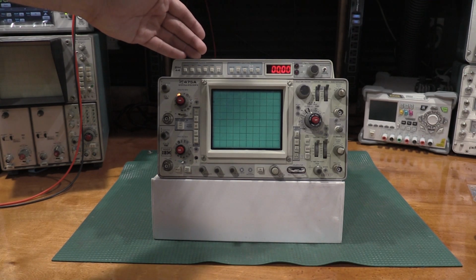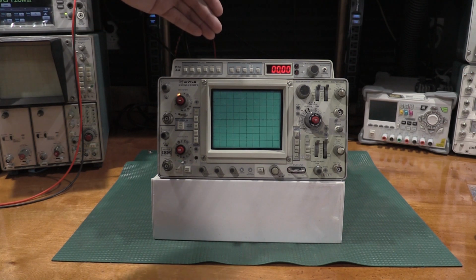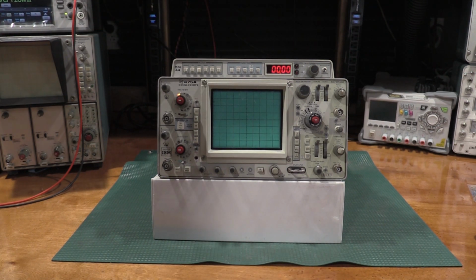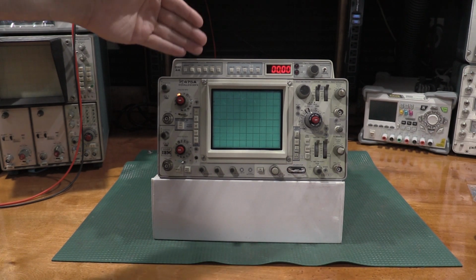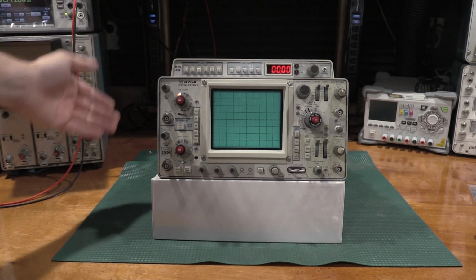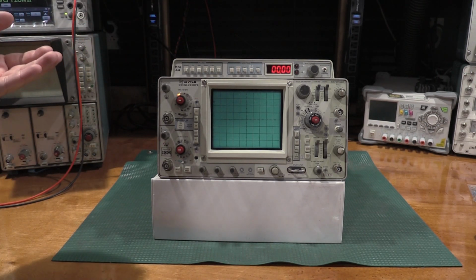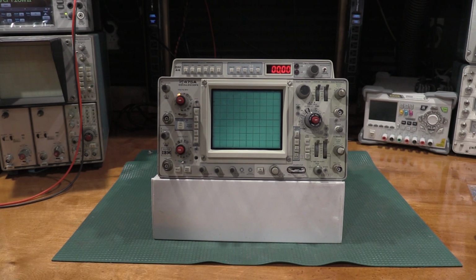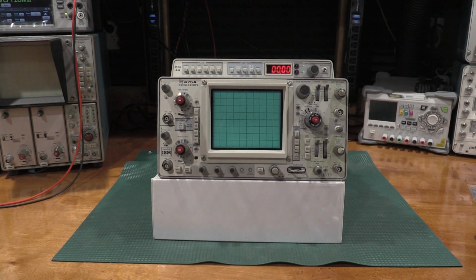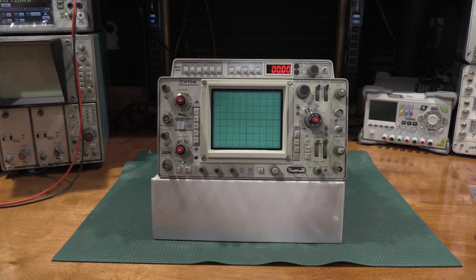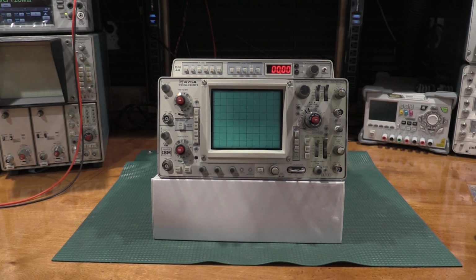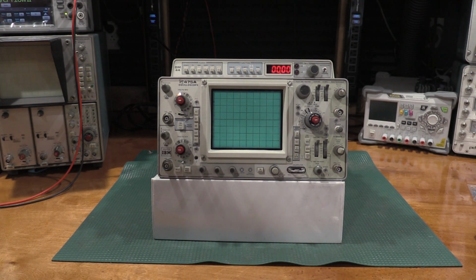The other thing with the DM44 is I won't be able to calibrate the temperature probe because I can test it. However, the alignment step for the probe aligns it to the probe. And for what the owner told me, the probe that came with it is not going back with it. So there will be one step that the owner of the scope has to do when they get it back, and that's just align the probe. You just put it in ice water and dial to 32. It's not that big a deal.